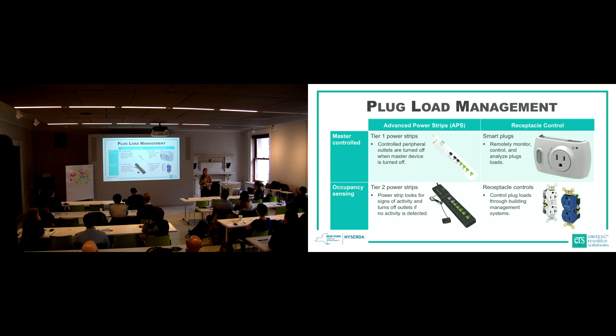And then control them to set them on a time schedule or whatnot based on the analysis that you find. The last option are physical receptacle controls. These are new outlets that you can install during a tenant fit out. These are a bit more invasive than the other options, but they're great because they connect into your BMS system so that you can control your plugs just like your lights or your HVAC. The additional benefit is that these can also be wired into existing occupancy sensors, so if you already have lighting occupancy sensors, these can work in the same manner.